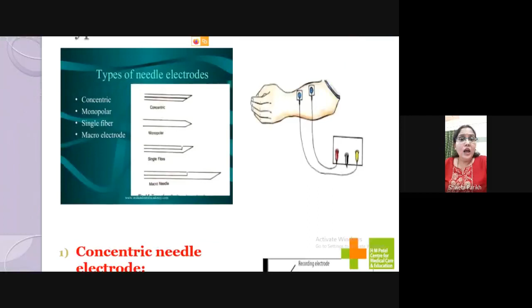Now, the concentric needle electrode is the most commonly used electrode in clinical practice. It consists of a 24 to 26 gauge needle with a fine wire in its lumen. If you can see, there is a fine wire inside the lumen. The active electrode is referred to the shaft of the needle, thus reducing the surrounding muscle noise. So that is the basic advantage of using the concentric needle electrode: we don't require a separate reference electrode and it does not produce much noise, so that we can hear other abnormal noise clearly.